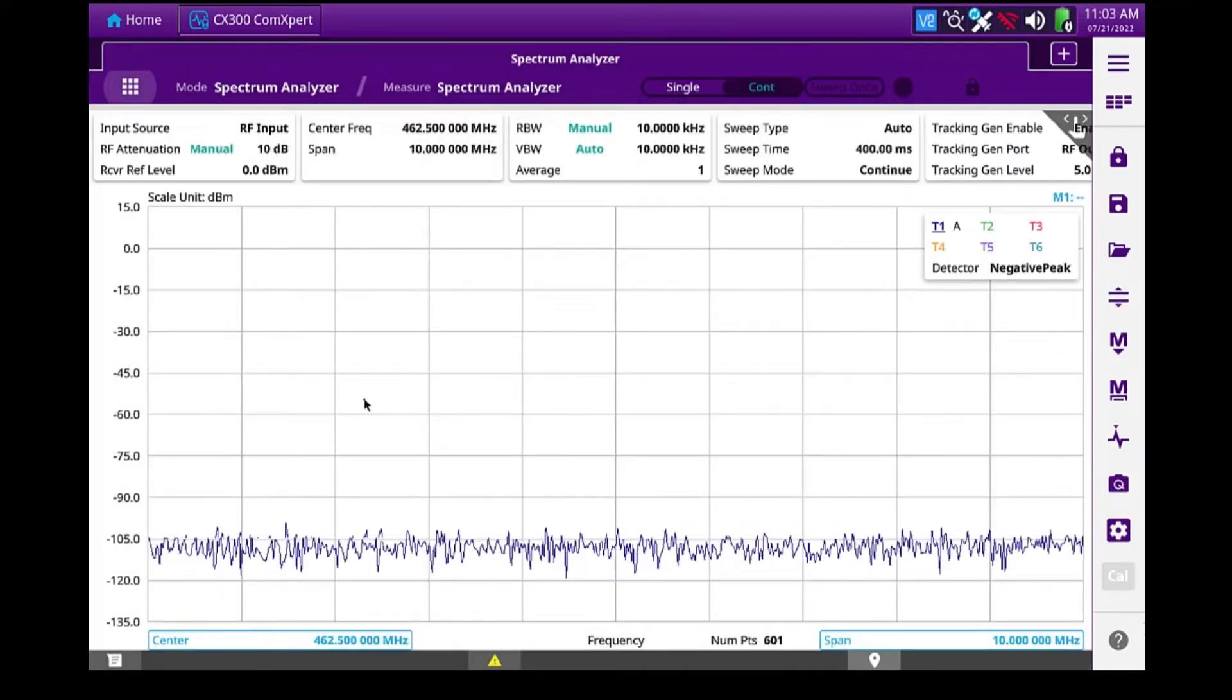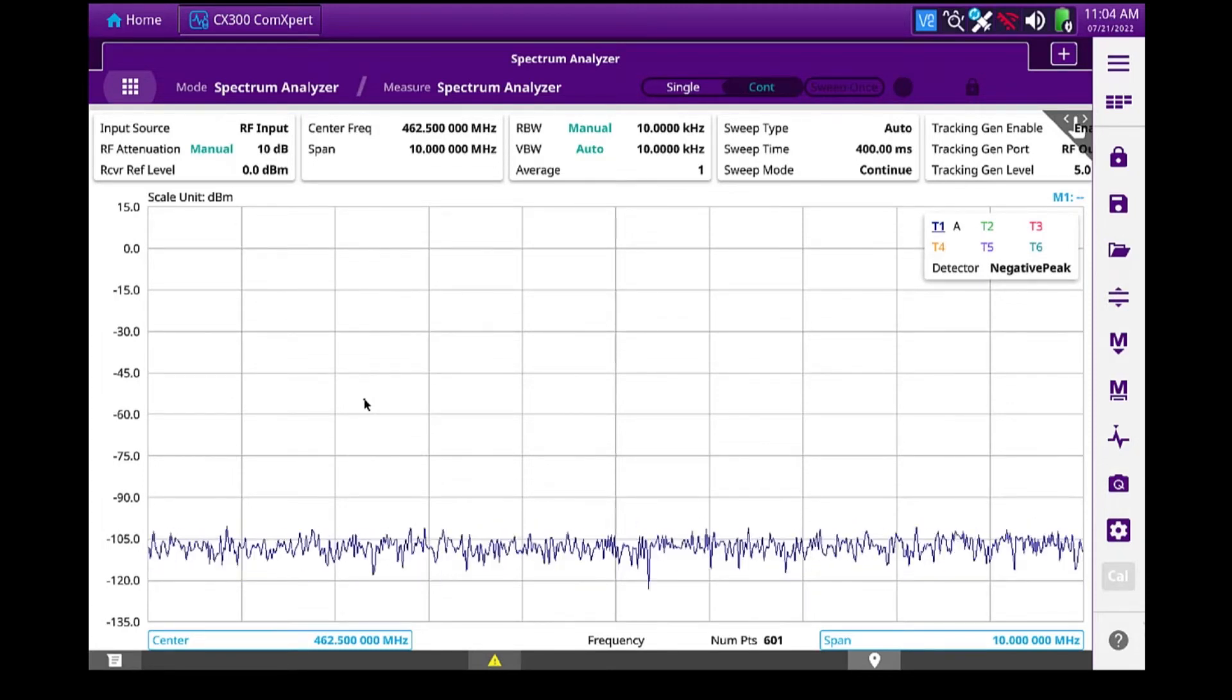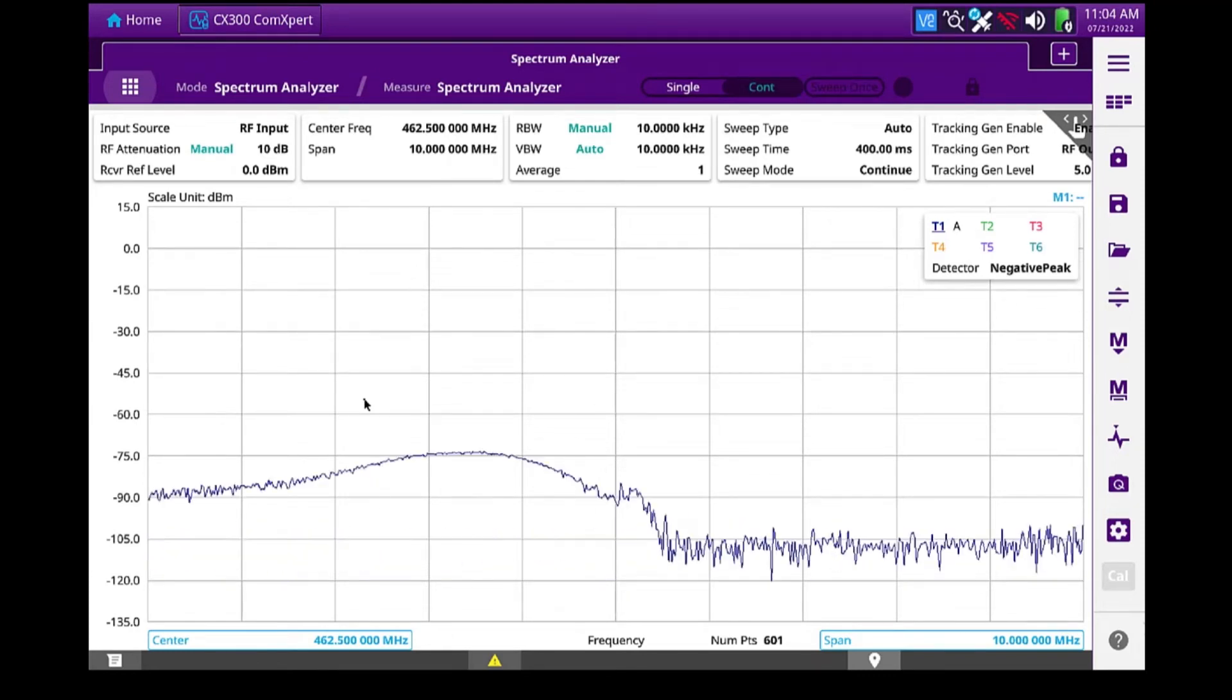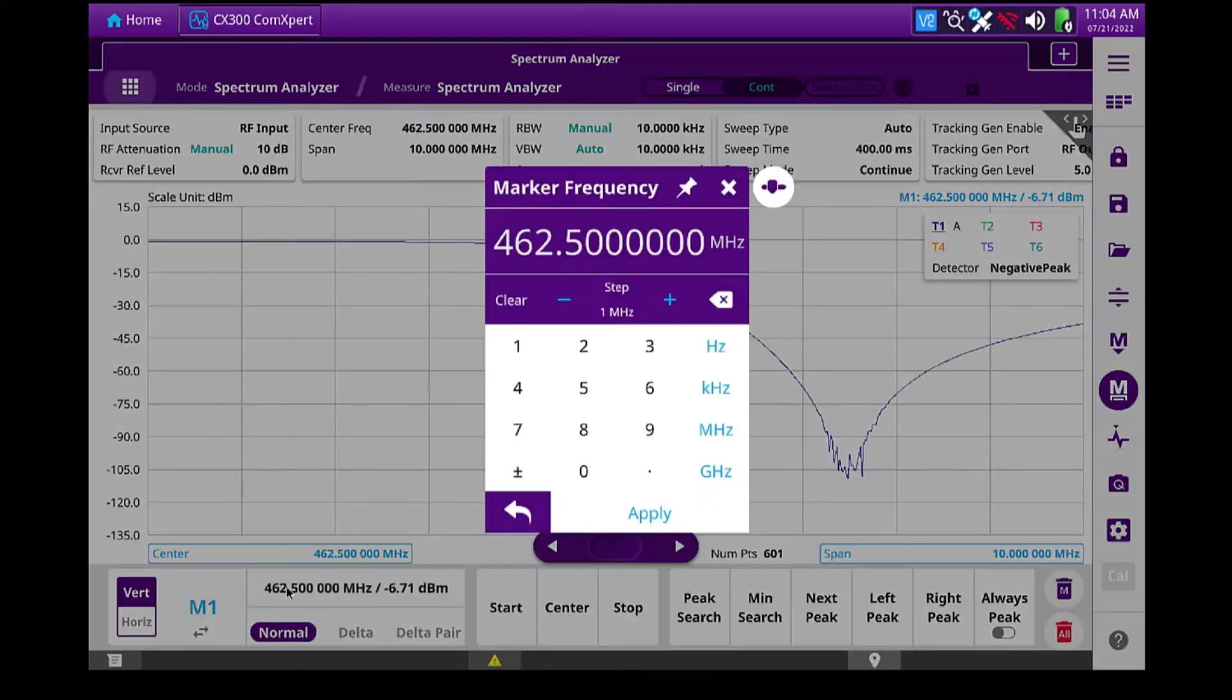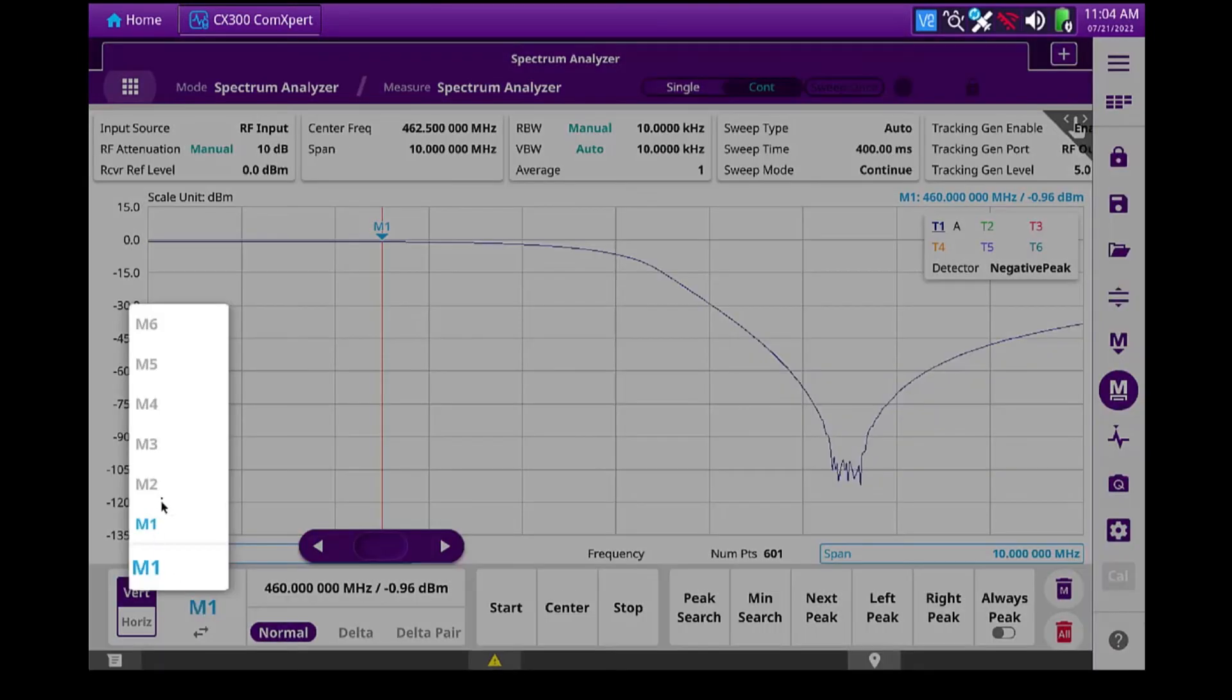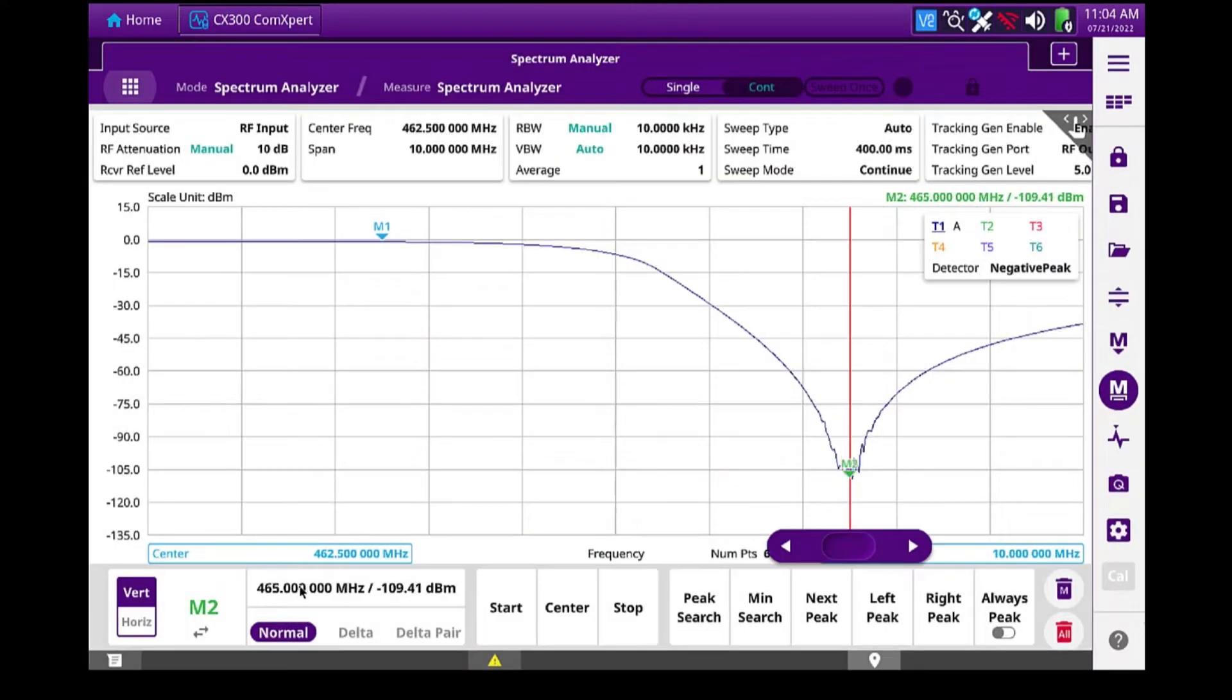So now I'm going to connect my RF input port to the duplexers antenna port. And I'm going to connect my RF output to the low side of my duplexer. And I have a 50 ohm termination connected on the high side. And this is what I'm seeing. I'm going to turn on a couple of markers with this marker icon. I'm going to set marker one to 460 megahertz because that's a target. And I'm going to click on this marker function and select marker two. And I'm going to set it to 465 megahertz. So now I have two markers enabled.